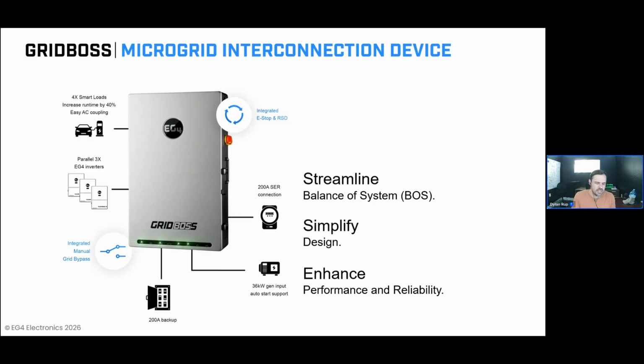And then, not to bury the lead, the load shedding capability of this unit really enhances the performance and the reliability of this system. Load shedding has repeatedly been shown to be one of the most cost-effective means to extend off-grid runtime for energy storage systems. Having that ability to intelligently manage those large loads often is the difference between a customer staying up during an extended outage and continuing to have power to the critical loads in their home, versus having a situation where their battery becomes drained and now they're in the dark because of ineffective management of loads within their home.